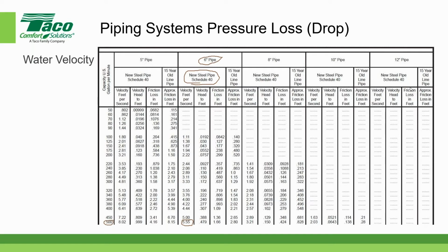So in other words, in this case, we're converting gallons per minute into cubic feet per second. And since it's a volumetric relationship, you don't have to compensate for temperature. Now, if you were calculating the mass rate of flow in pounds per hour, then you would have to compensate for temperature. So in this case, the velocity is a function of the volumetric flow and not based on the mass rate of flow. Hopefully that answered that question.